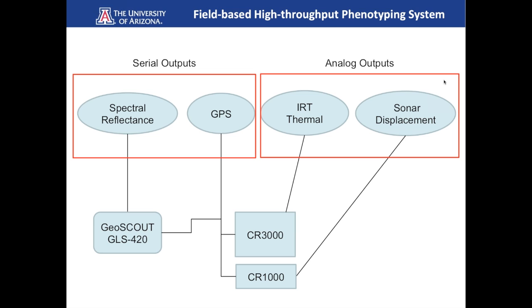So let's talk about measurements and communication. Analog measurements can be done extremely fast, much faster than digital. And when I say digital, I'm talking about the serial communications. For higher rate sampling, and that's, relatively speaking, faster than, say, 2 hertz, it's a good idea to use sensors that have proportional analog output, such as a current loop or a voltage output, rather than serial sensors.